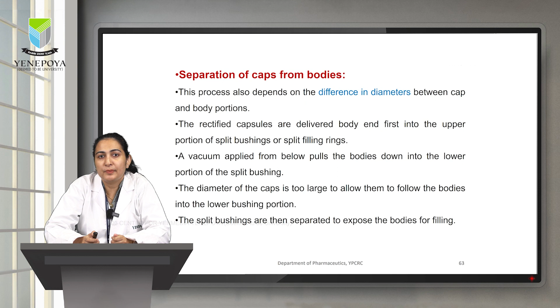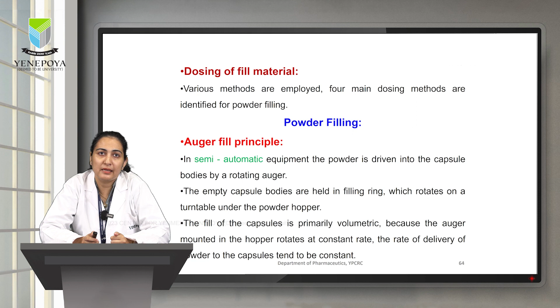Next is dosing of fill materials. Various methods are employed. Four main dosing methods are identified for powder filling. The first principle involved is the auger fill principle. In semi-automatic equipment, the powder is driven into the capsule bodies by a rotating auger. The empty capsule bodies are held in a filling ring which rotates on a turntable under the powder hopper. The fill of the capsules is primarily volumetric. Because the auger is mounted in the hopper, it fills at a constant rate, and the rate of delivery of the powder to the capsule can be kept constant.